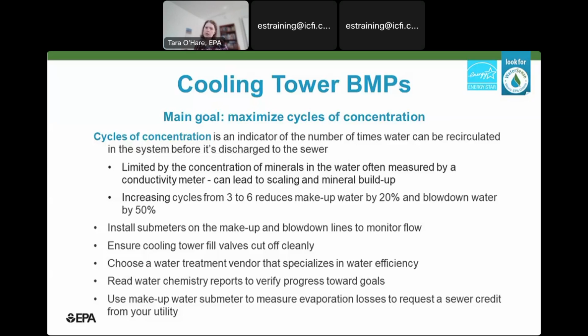Most of these systems have a water treatment vendor that really helps to keep the system in order. So you want to talk to them about why you want to save water and make it part of the work that they're doing. Oftentimes they'll leave a report when they do a visit, and you can take this report and read it to look at the progress towards your goals. So if you're trying to move from water being used 3 times to water being used 6 times, you want to make sure that's actually happening and that you're getting those savings as you expect.